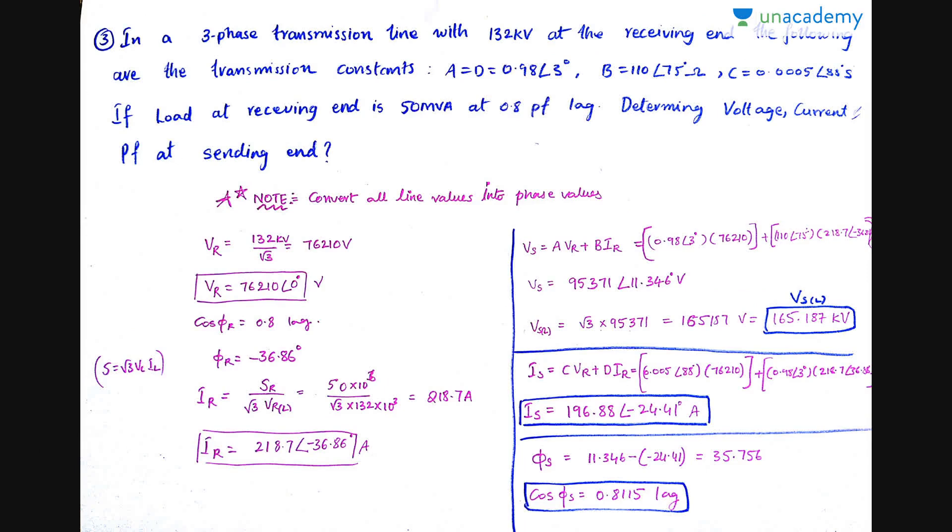Sending end current - similarly, you just put in all the values. You get Is as 196.88 at angle minus 24.41 amperes. I want to find the sending end power factor also. Power factor is - sending end power factor will be cos of φs, where φs is the angle between sending end voltage and sending end current. So sending end voltage angle minus current angle - the gap between both of the vectors of sending end voltage and sending end current is 35.756. Put cos and then you get 0.8115 lag as the answer. This is how we can solve a transmission line problem using ABCD parameters when given.